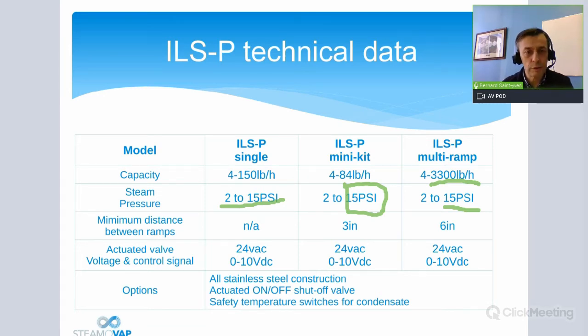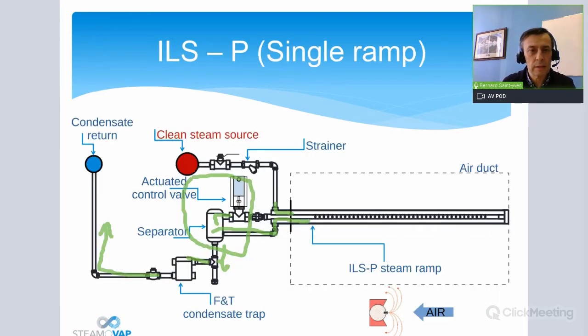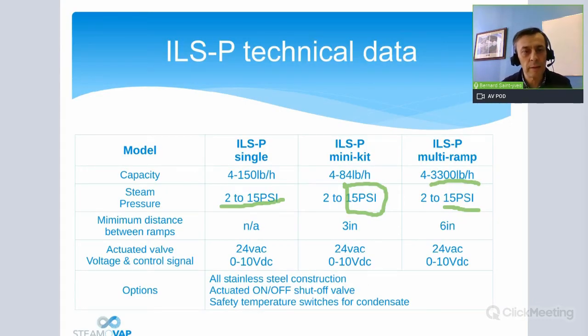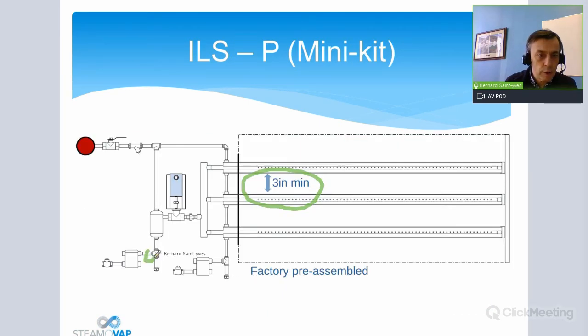We can also offer the actuated on-off shut-off valve, to replace this one. So this one can be an electric actuated valve instead of a manual one, if you want a signal shutting off the humidifier when there is no demand. And there is the safety temperature switch for the condensate. This will protect the system from any trouble at the steam trap. In case the steam trap fails closed, the temperature switch or thermostat will be placed here, and the condensate will build up and come here.